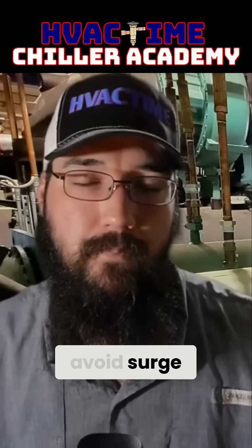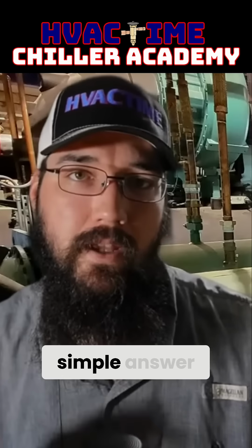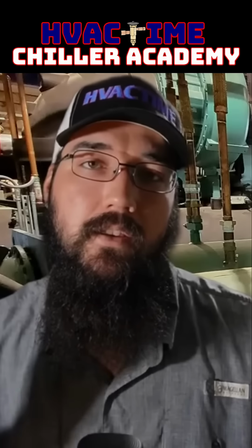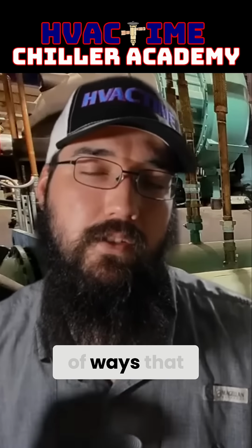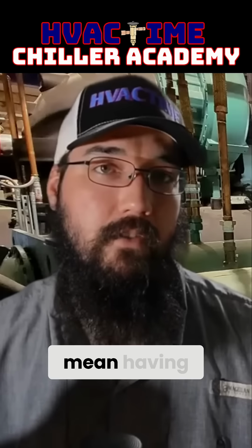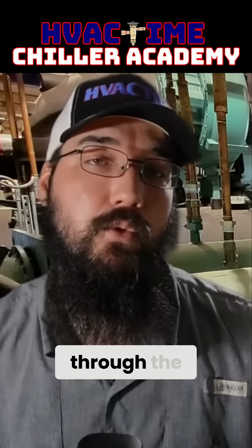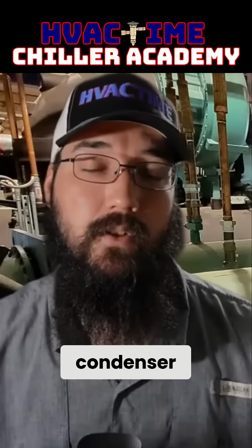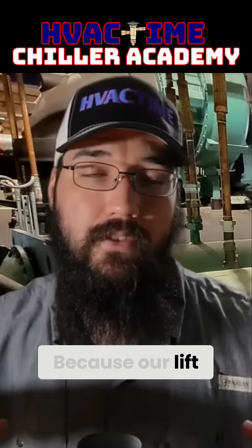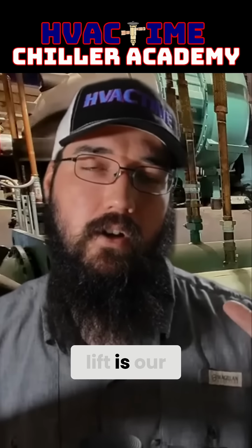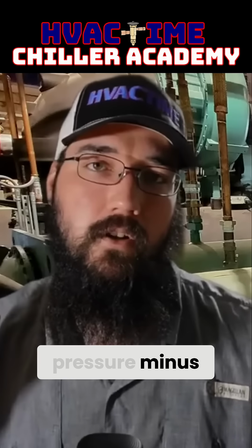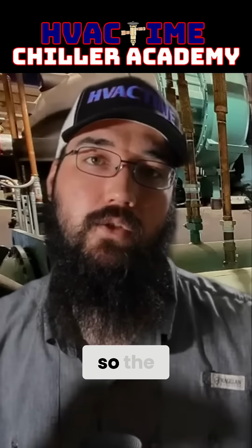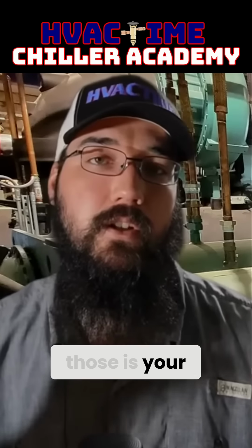So how can I avoid surge? A short, simple answer is keep your lift under control. Now, there's a lot of ways that we have to do that. That could mean having proper GPM through the heat exchangers, the evaporator and the condenser, because our lift, the definition of lift, is our condenser pressure minus our evaporator pressure. So the difference between those is your lift value.